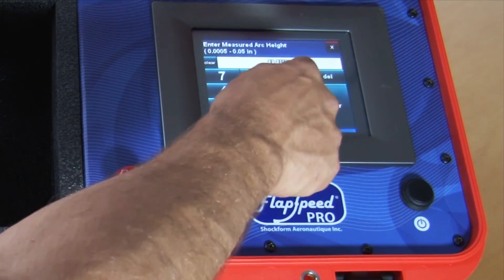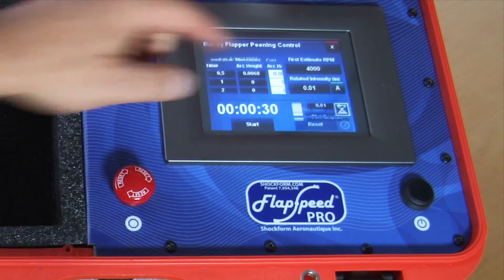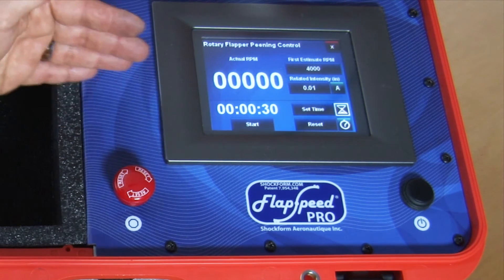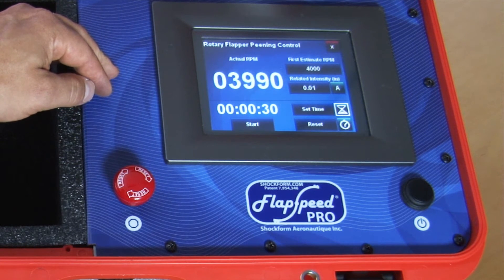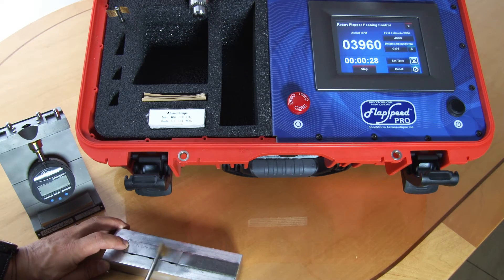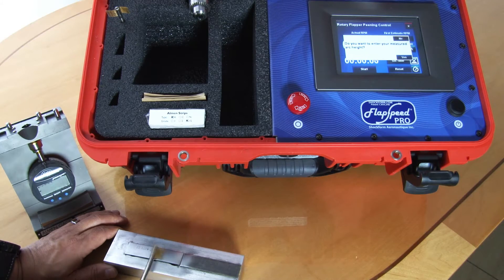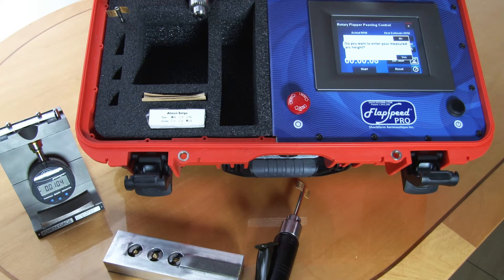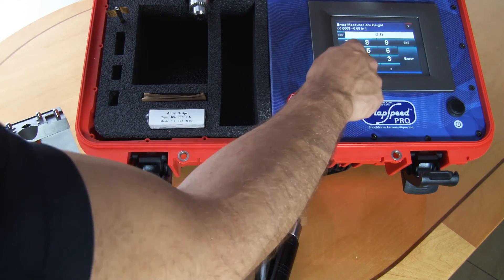To do the second point, we press on the second button. We see that we're at 30 seconds again because we're doubling the time — going from 30 seconds to a minute, so we need to add 30 seconds. We start the unit, it'll reach 4,000 RPM, and when we're happy we press the start button. We'll measure the second arc height — we're getting 0.0104 — and we'll enter that into the system: 0.0104.